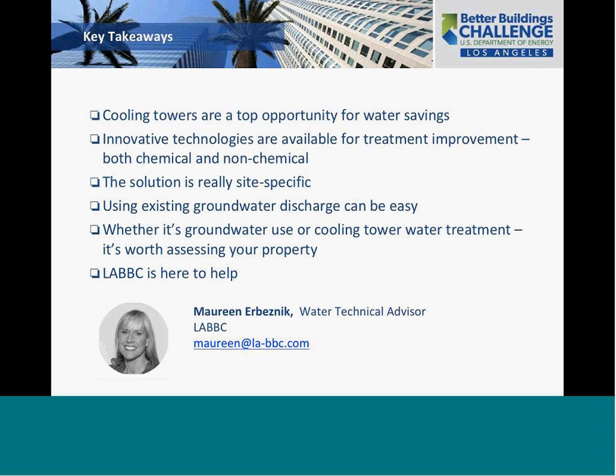Interesting. So when you're looking at a target size, is it the cooling tower size or the cycles of concentration? Both. Okay. Yeah, both we want to look at. There's definitely diminishing returns. If you have high cycles already and you have a small tower, it's probably minimal savings. The larger the tower, the better the general opportunity is, and the lower the cycle rate, again, the better the opportunity is for overall water savings. We typically like to start looking at facilities with towers in excess of, say, 200 or 300 tons, unless there are multiples on the site.